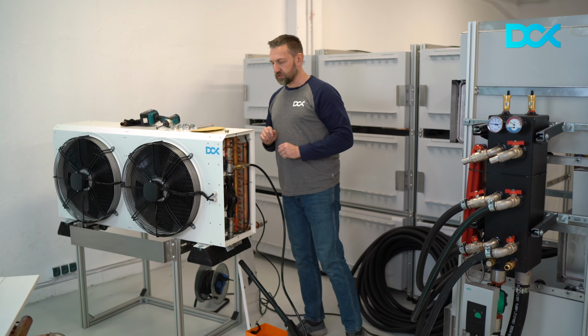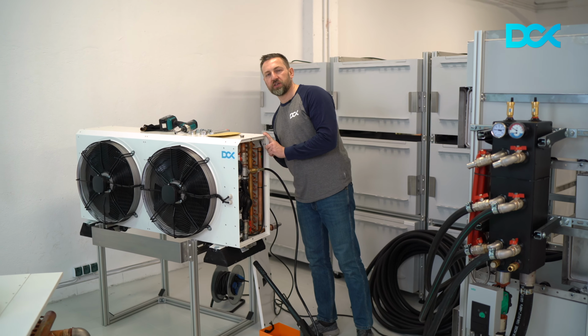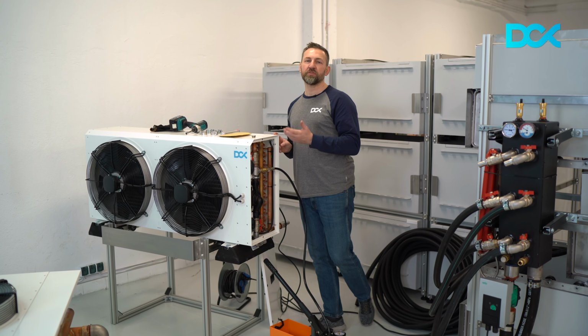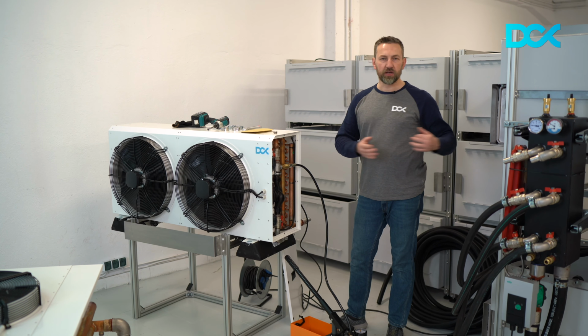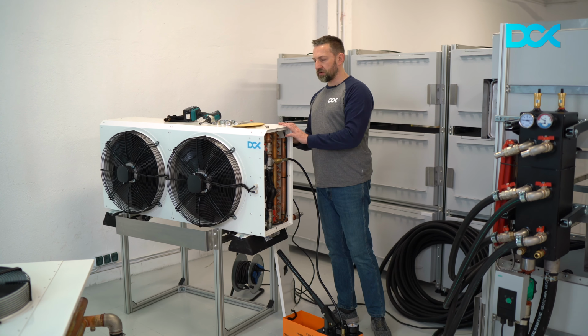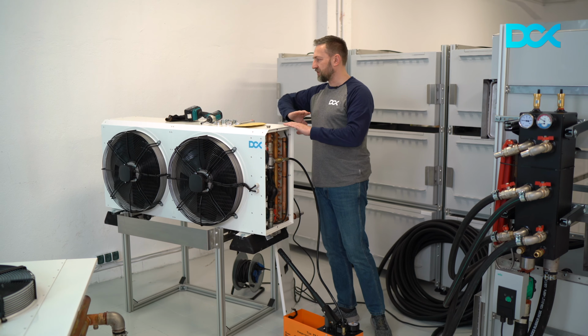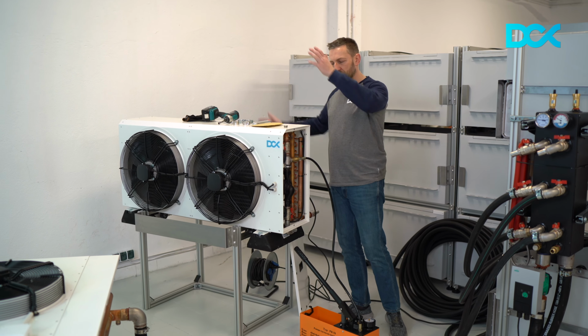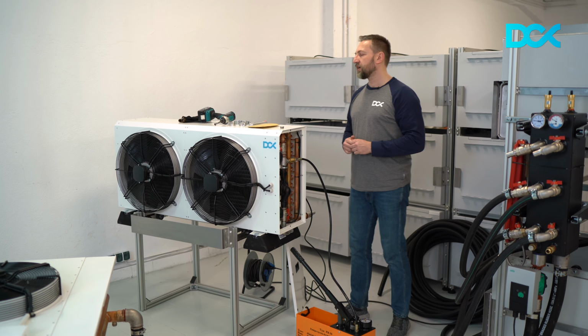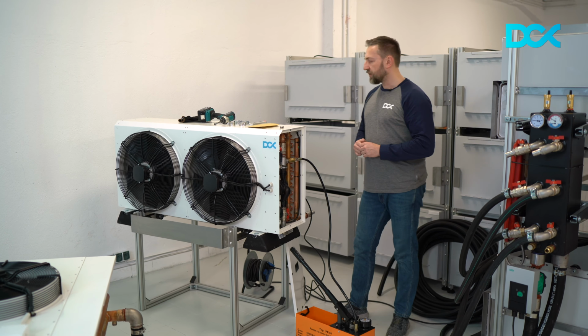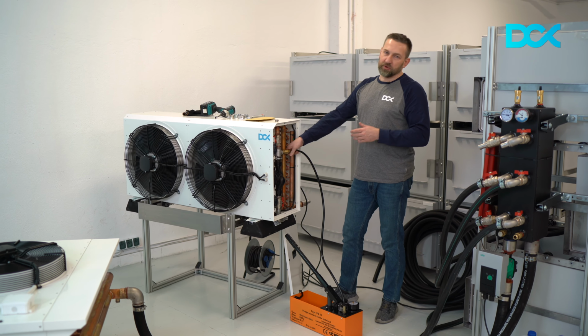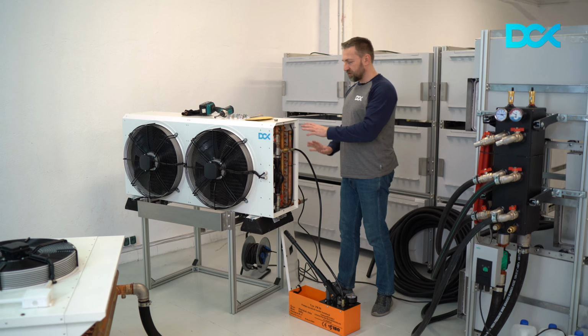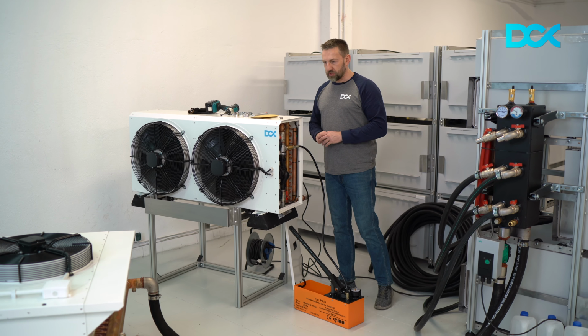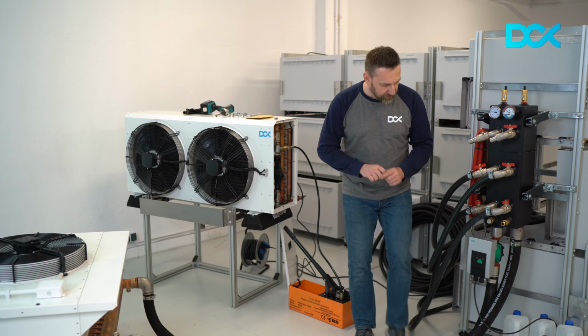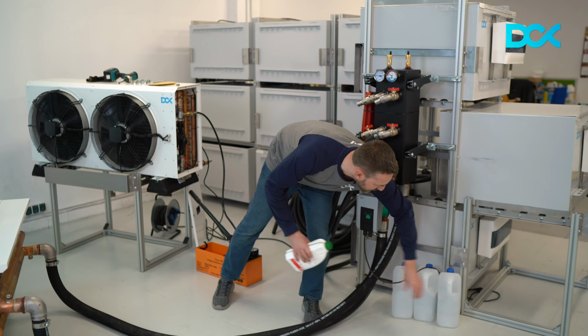As mentioned previously, the dry cooler should be located in the vicinity of the enclosure, up to 15 meters away. The dry cooler must be standing outside in a horizontal position, it will not work vertically. It uses water or water glycol mixture, so we're not running the more expensive dielectric fluid here, just typical water or water glycol mixture. What we use is demineralized water along with...